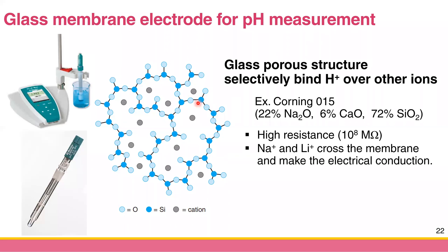Most of it is silicon, with some sodium and calcium. The glass membrane has high resistance — because in potentiometry you want a constant potential, and high resistance prevents current from shifting your potential result. They also dope sodium ion and lithium ion into the glass membrane to provide electrical conduction, because although you need high resistance, you still need some electrical connection to make a complete circuit.